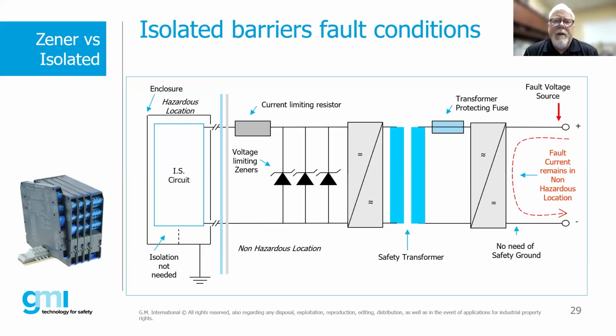And again, the same thing in the isolated barrier under a fault condition. Just like we saw in the previous slide, we're using that safety transformer so we don't have that direct connection. Typically under a fault condition, we don't have these problems that we would have with a Zener barrier.